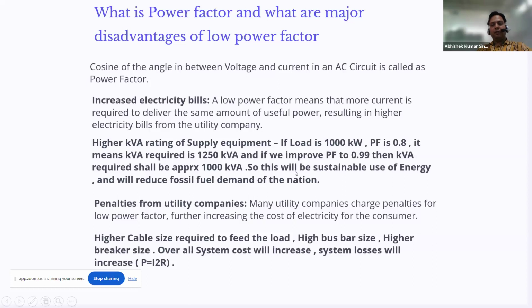If the power factor is low, like 0.8, then what is happening? The requirement is 1250 kVA. When the requirement is 1250 kVA, the cable size will increase, the bus bar size will increase, the breaker size will increase. So the overall system cost will increase. The losses, which are P equal to I square R, as we all know. The more current flows into the system, the more losses will happen in the system.